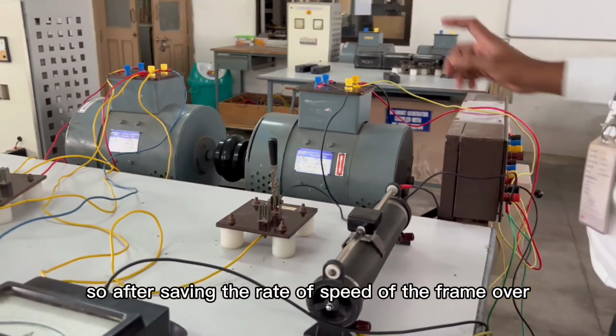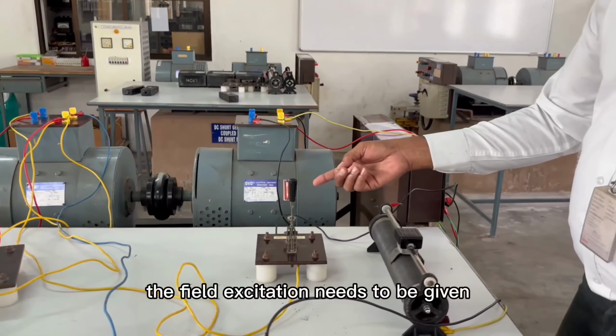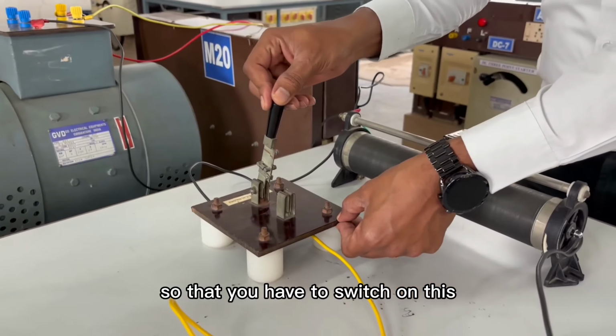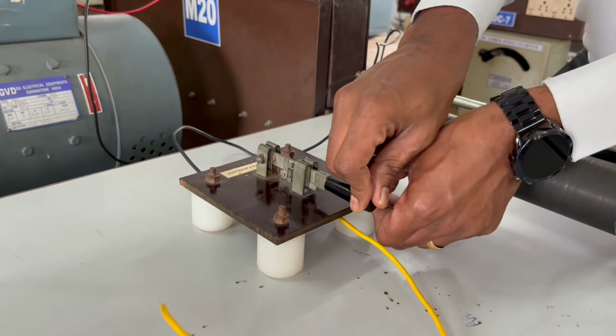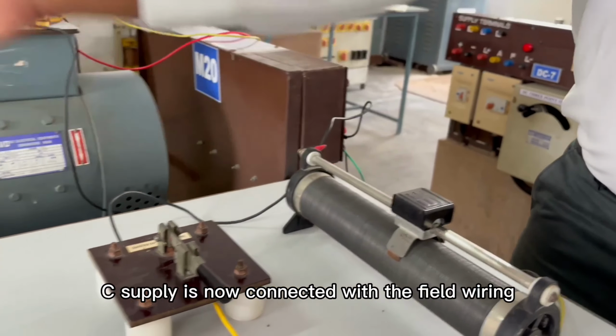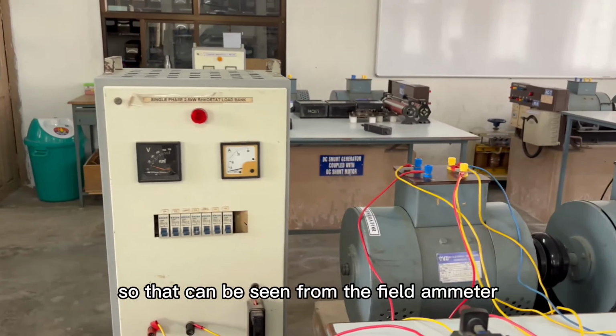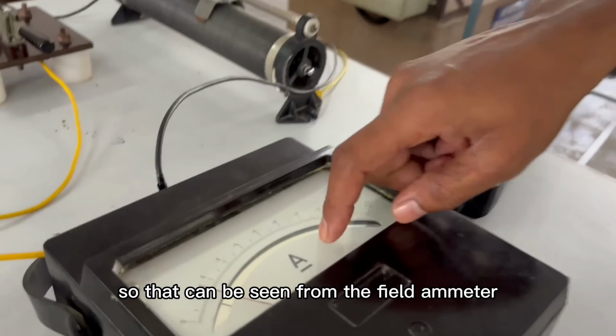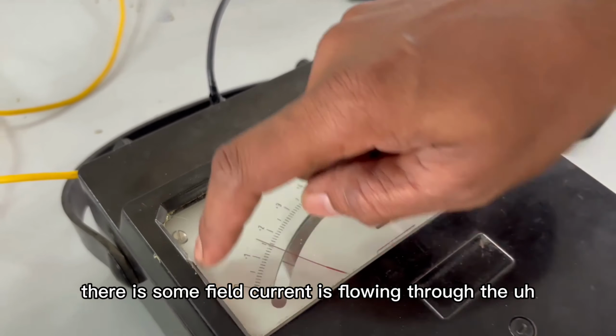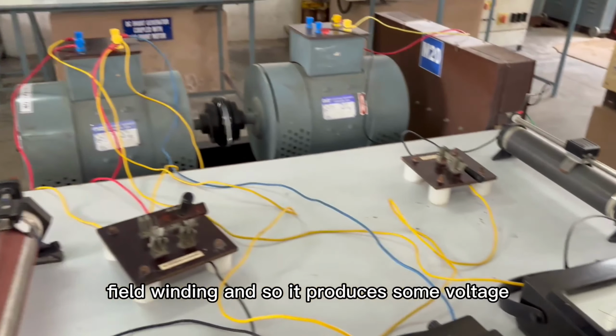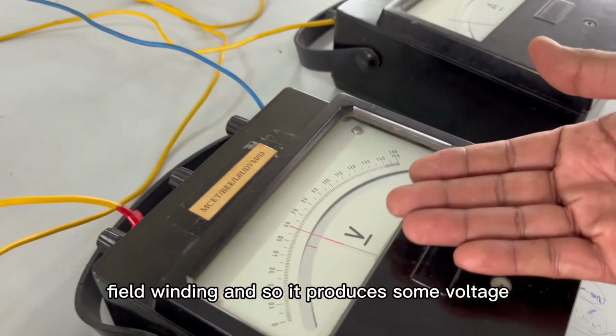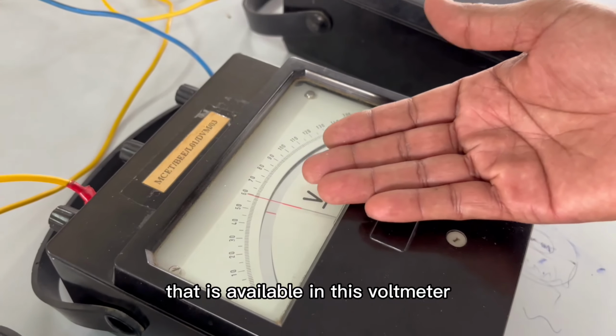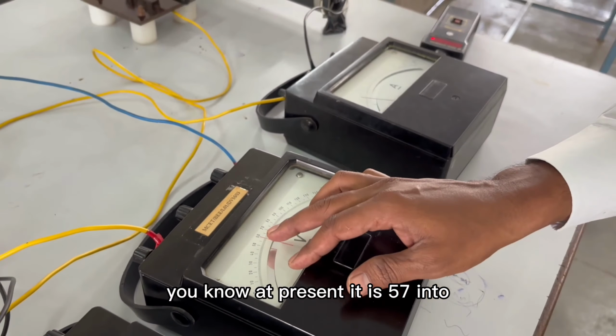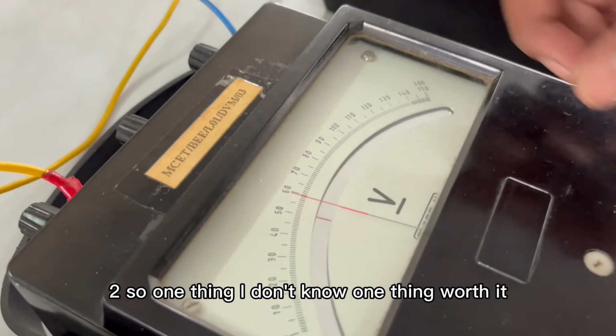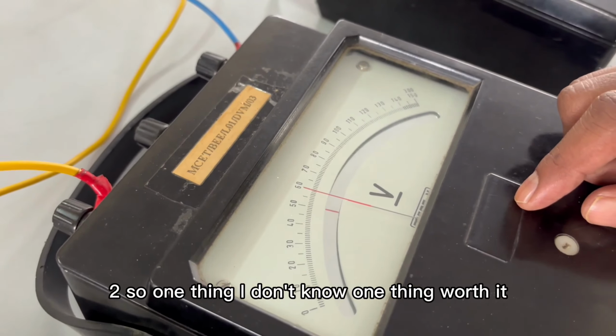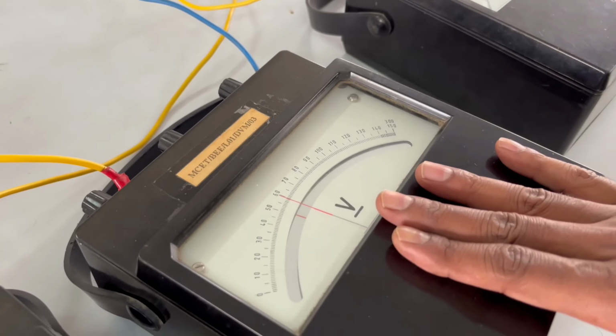After setting the rated speed of the prime mover, the field excitation is to be given, so you have to switch on this SPST. So the external DC supply is now connected with the field winding. That can be seen from the field ammeter. Some field current is flowing through the field winding, and so it generates some DC voltage that is available in this voltmeter. At present it is 57 into 2, so around 110 volt is generated.